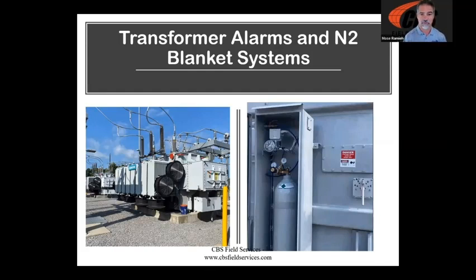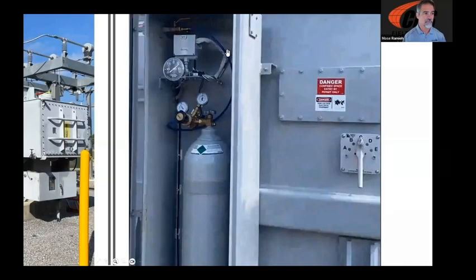The simple method of just checking the gauge. Now I've got a picture of that gauge right here. The simple process of just checking that gauge, making sure I've got nitrogen both in my tank and in my system, keeps that moisture from getting into the load tap changer. But when that moisture got in there, it had to, of course, get repaired.